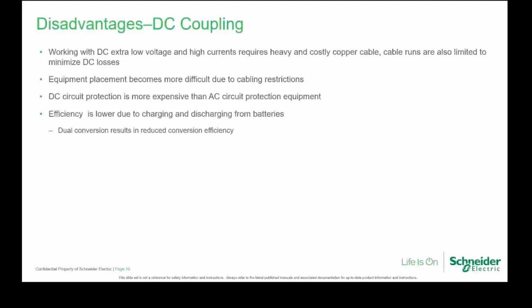Efficiency is lower due to charging and discharging the batteries. This is where every time you charge a battery, you lose some. You've got to put more energy in than you can get out. When you're discharging, you've got to limit how much energy you can actually draw from the batteries. So dual conversion results in reduced conversion efficiency.